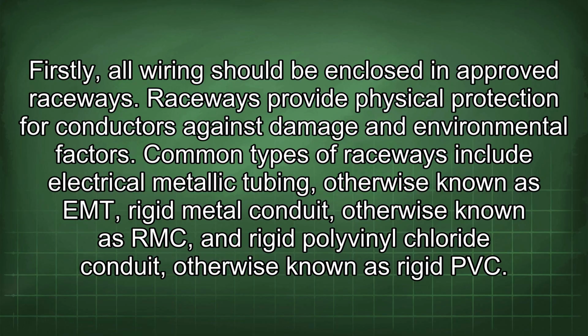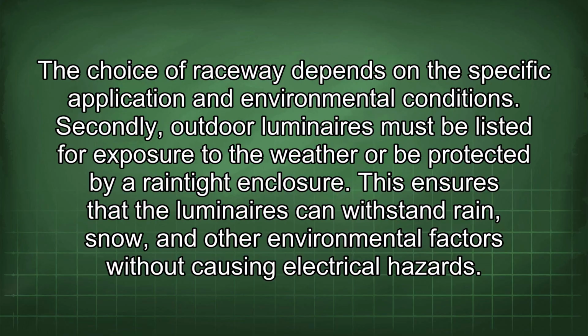Common types of raceways include electrical metallic tubing, otherwise known as EMT, rigid metal conduit, otherwise known as RMC, and rigid polyvinyl chloride conduit, otherwise known as rigid PVC. The choice of raceway depends on the specific application and environmental conditions. Secondly, outdoor luminaires must be listed for exposure to the weather or be protected by a raintight enclosure. This ensures that the luminaires can withstand rain, snow, and other environmental factors without causing electrical hazards.